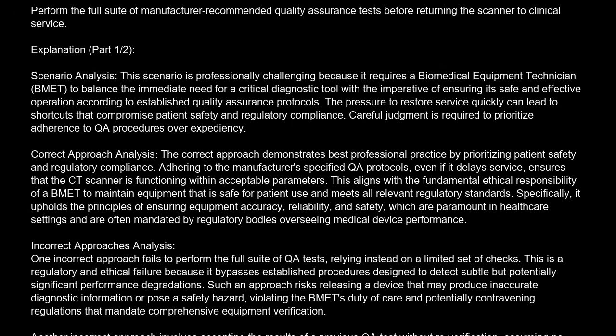Correct answer is D. Perform the full suite of manufacturer-recommended quality assurance tests before returning the scanner to clinical service. Explanation. Scenario analysis. This scenario is professionally challenging because it requires a biomedical equipment technician, BMET, to balance the immediate need for a critical diagnostic tool with the imperative of ensuring its safe and effective operation according to established quality assurance protocols. The pressure to restore service quickly can lead to shortcuts that compromise patient safety and regulatory compliance. Careful judgment is required to prioritize adherence to QA procedures over expediency.